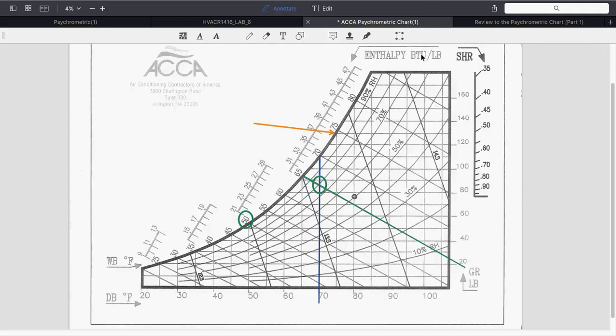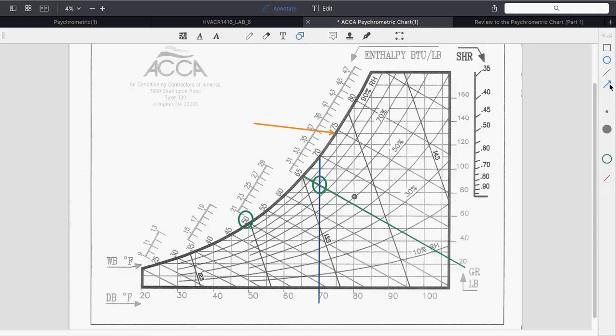Looking at where the crossing falls between the 70% and 90% lines, that curved line represents 80% humidity. If the wet bulb is lowered to about 55 degrees, the crossing drops significantly — the humidity would be closer to around 40%. When reading humidity, always round to the nearest line.